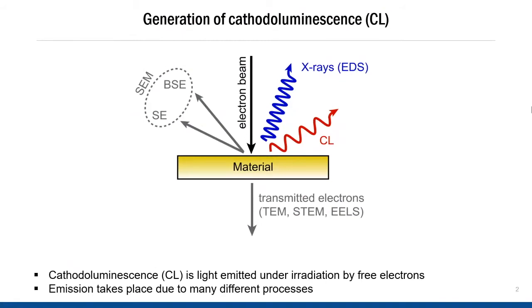You can have generation of X-rays, which are then imaged using EDS. You can have low energy secondary electrons that are generated or high energy backscattered electrons, and both of these are imaged in the SEM using standard SEM detection techniques. If the material is thin enough and the energy of the electron beam is high enough, it may penetrate and come out the other end of the material. In that case, you can image transmitted electrons using TEM or STEM or electron energy loss spectroscopy. What can also happen is that you can have the emission of light, which takes place due to many different processes, all of which fall under the umbrella of cathodoluminescence.